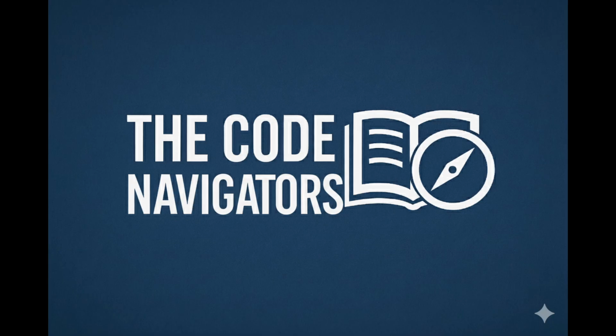That's the idea, and that leads directly to Section 1017, exit access travel distance, how far you're allowed to walk to get to safety. And this is another one of those things where the numbers are critical for exams, and they live in Table 1017.2. They do, and you can really see the code's risk assessment here. The distance changes based on what the building is used for, and you guessed it, whether it has sprinklers. Let's see an example. For a standard office, Group B. For a Group B without sprinklers, your max travel distance is 200 feet. But with sprinklers, it jumps all the way to 300 feet.